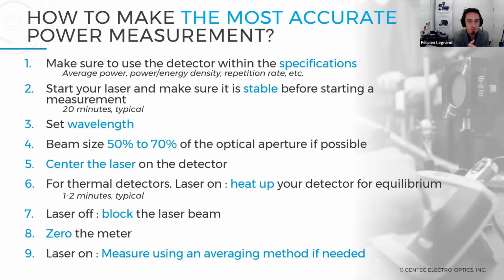And then for thermal detectors, not for photodiodes, since we're focusing more on high power applications here: for thermal detectors, have the laser on and heat up the surface and the detector itself, to have it in thermal equilibrium, so you have the full system stable. Try to limit the air flows and air circulations.